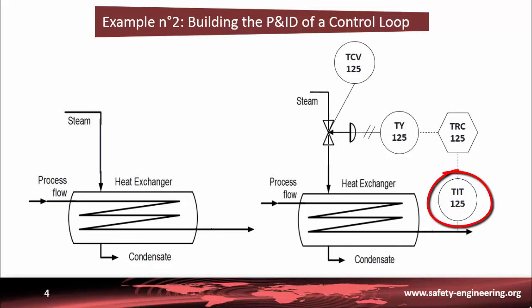First of all, we need a temperature sensor at the process flow outlet of the heat exchanger, which indicates and transmits the measured value as an electrical signal to a controller. The controller is often a recorder as well to record all the measured values. The controller then sends an electrical signal to an I/P converter indicating how much the valve should open or close. The I/P converter will then convert this signal into a pneumatic signal, which in turn gets sent to the pneumatic control valve so that it can regulate the opening.